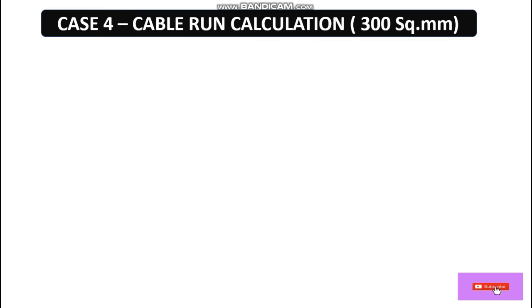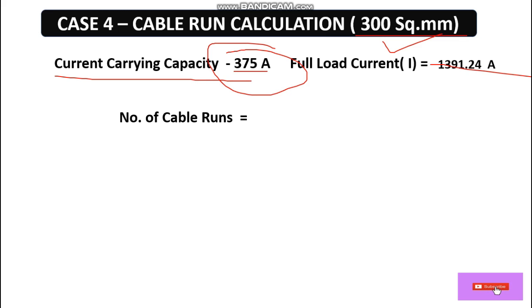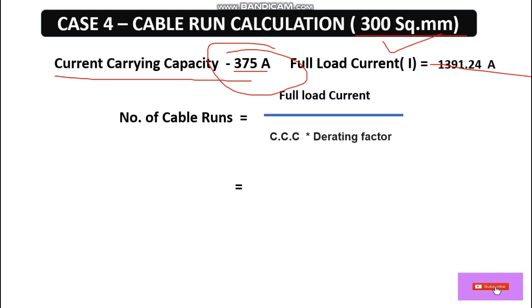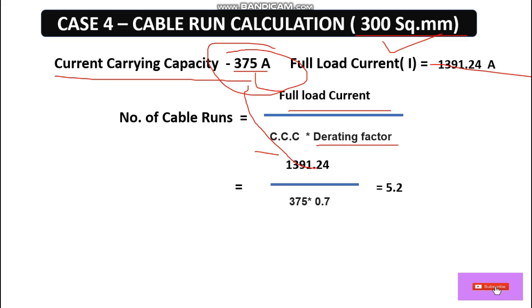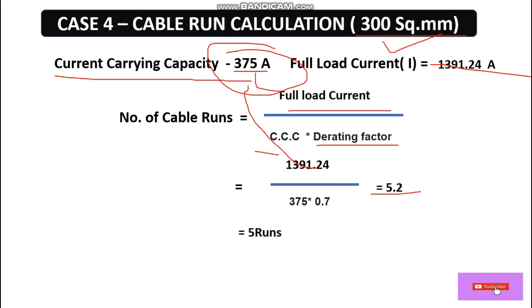Case 4: Let's decrease to 300 square mm. Looking at the catalog, the current carrying capacity of 300 square mm cable is 375 ampere. Full load current is 1391.24 ampere. Number of cable runs = 1391.24 / (375 × derating factor) = 5.2 runs, so 5 runs. For both 400 square mm and 300 square mm cables, 5 runs are required.